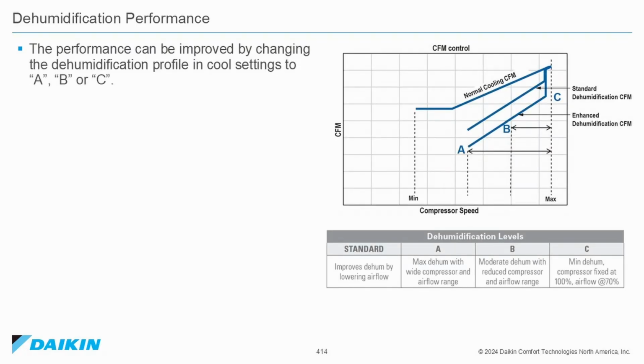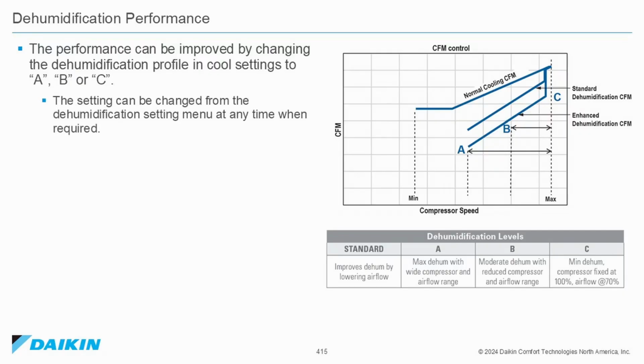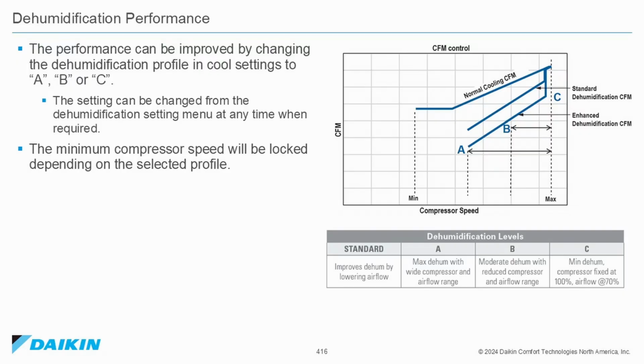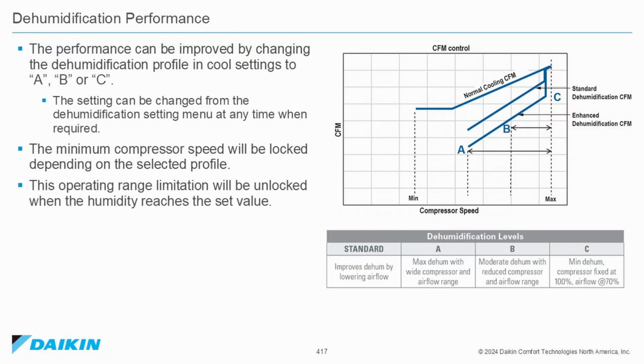Dehumidification performance. The performance can be improved by changing the dehumidification profile in cooling settings to A, B, or C. The settings can be changed from the dehumidification setting menu at any time when required. The minimum compressor speed will be locked depending on the selected profile. The operating range limitation will be unlocked when the humidity reaches the set value. There must be a call for cooling and a demand for dehumidification.